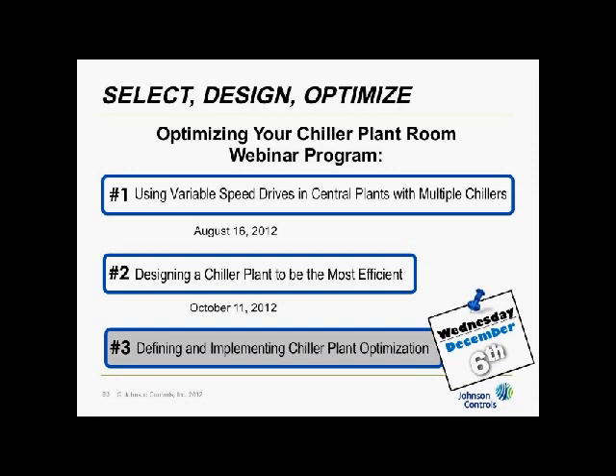How would you optimize control VFD condenser water pump and VPF systems? How to balance flow over chillers if they have a different rated capacity? Well, you could put a pressure sensor and vary the speed depending upon what chillers are running. You could have an algorithm to vary the speed with load, meaning to maintain delta T across the condensers. Whatever condensers you got, maintain the delta T. As long as they're balanced to start with, then they ought to ramp down at the same basic proportion. So maintain delta T is a good way to do it too. That's the same thing as saying I want to reduce with load.